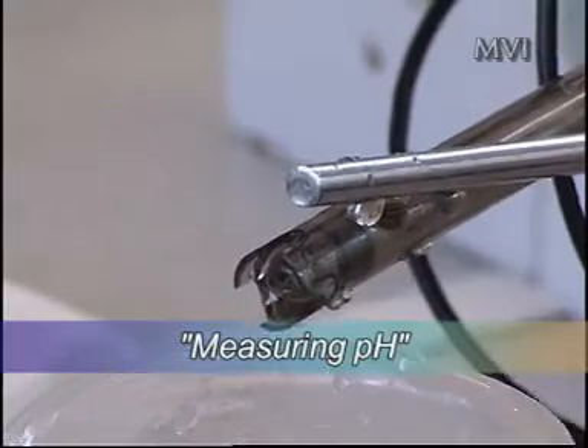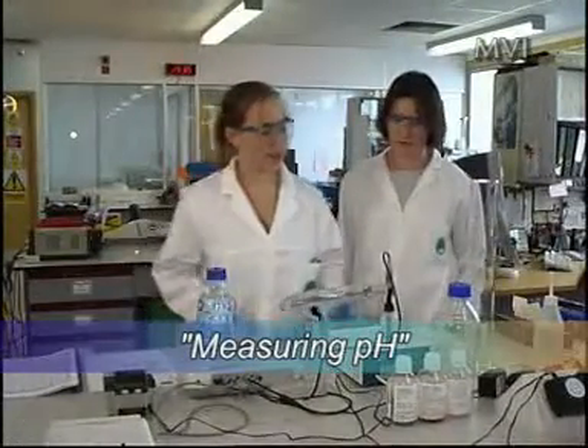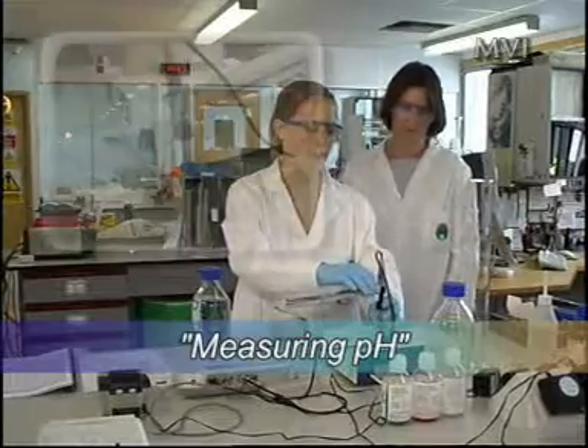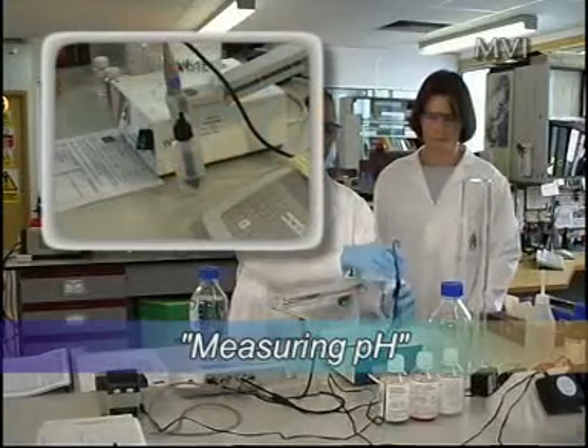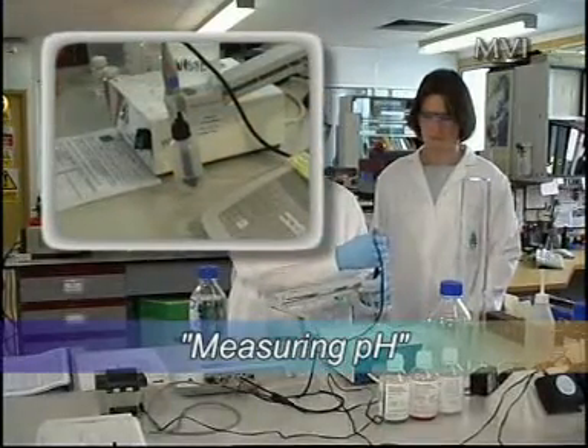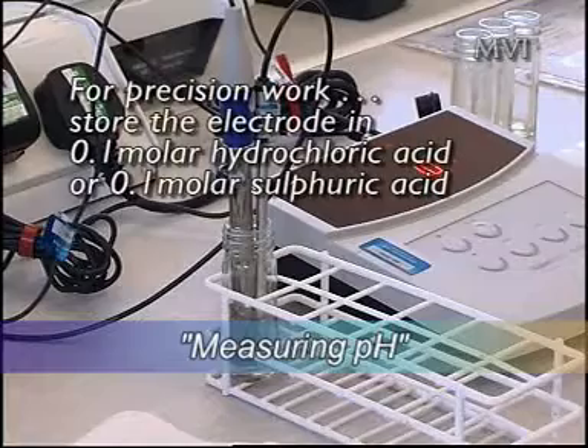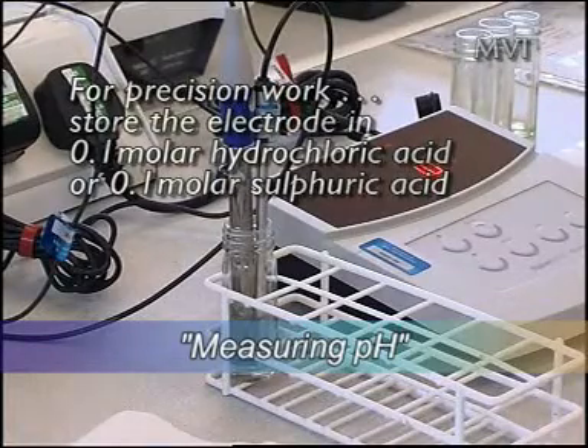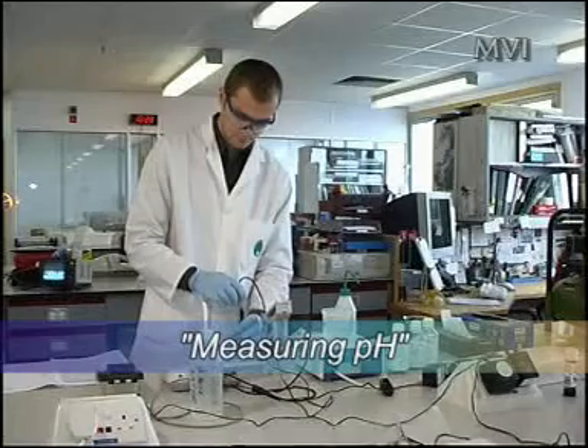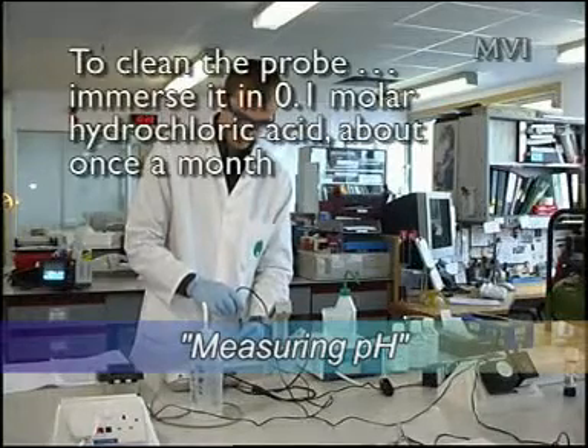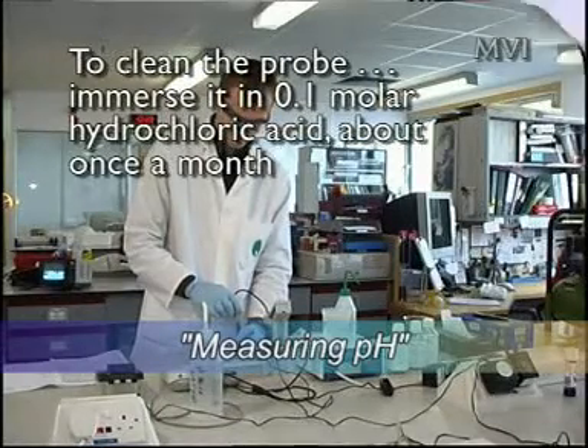The glass electrode is not allowed to dry out. In most pharmaceutical laboratories, electrodes are stored in distilled water or deionized water, but for precision work, it is probably best to store the electrode in 0.1 molar hydrochloric acid or 0.1 molar sulfuric acid. Regardless of which, it is worth cleaning the probe by immersing it in 0.1 molar hydrochloric acid.